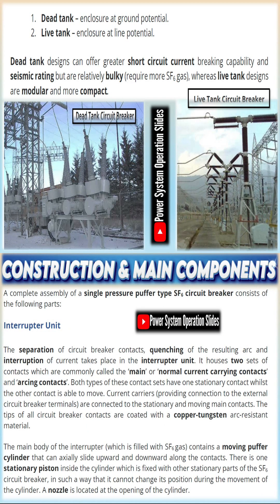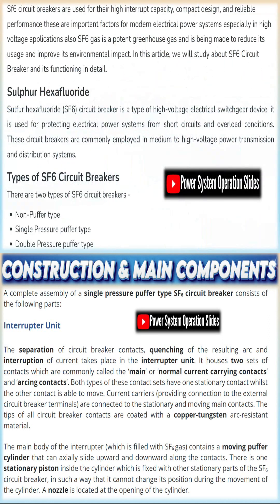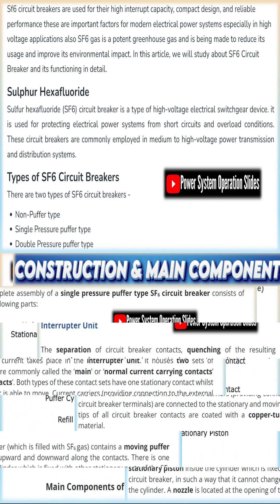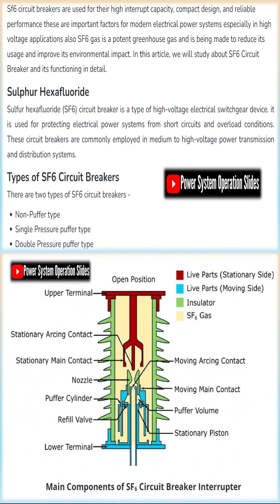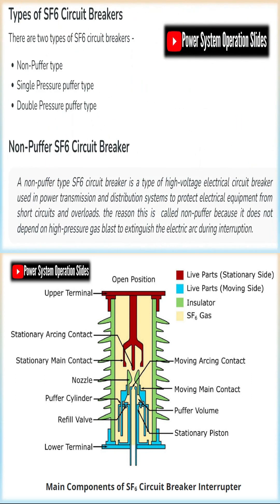Sulfur hexafluoride gas is a colorless, odorless, non-flammable, and chemically stable gas with excellent dielectric and arc-quenching properties, making it ideal for use in high-voltage switchgear. One of its primary applications is in SF6 circuit breakers, which are widely used in modern power systems for protecting equipment by safely interrupting high fault currents.